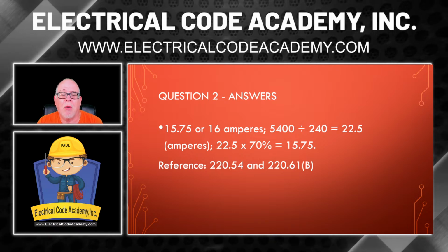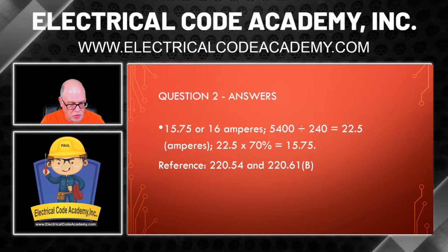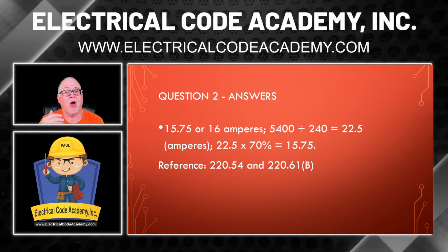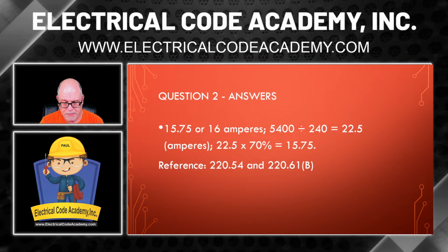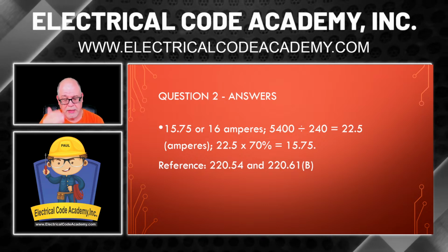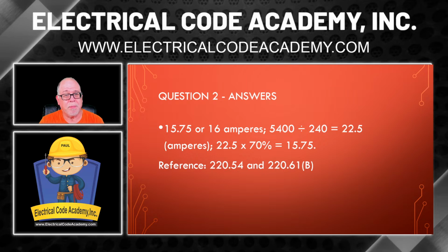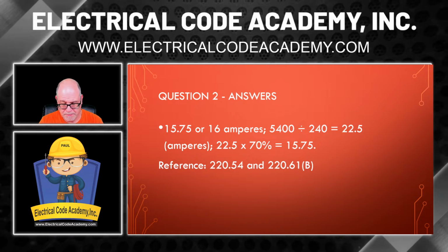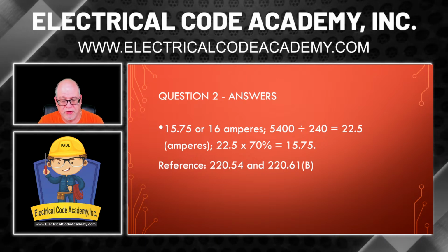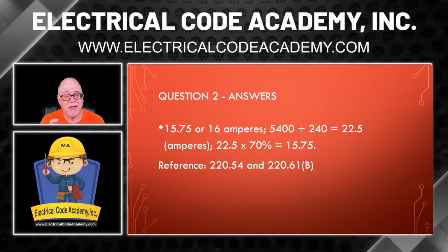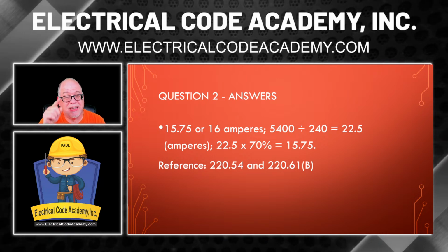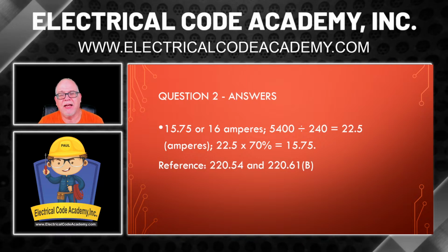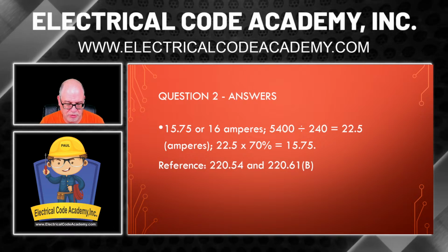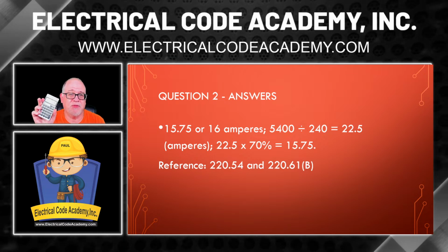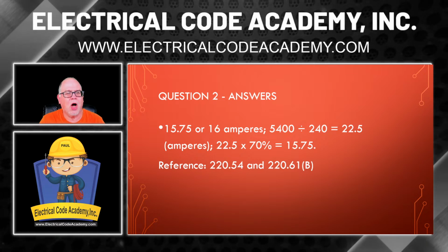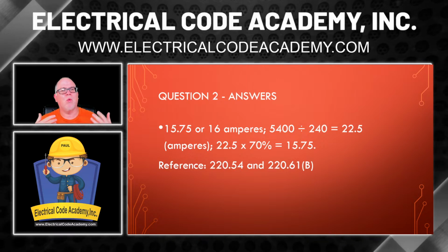Now, I want to talk about the other way you could have done this. One other way you could have done this is start with our full value, our 5,400, and you could have multiplied that by 70%. That gives you 3,780 VA. Then you could take that and divide that by 240 volts. And that also gives you 15.75. Always remember, there are many ways that you can do this.